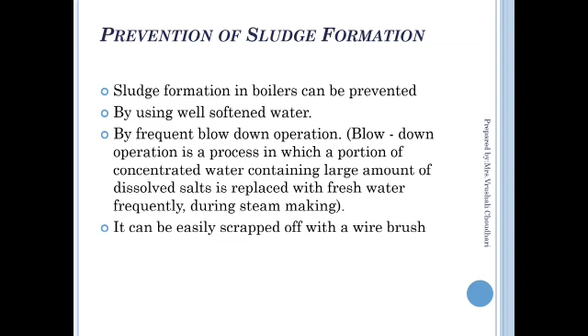Sludge is a soft, loose, slimy precipitate, while scale is a hard deposit. When sludge forms, it is non-adherent. It is not going to stick on the walls. It is going to float on the surface of the water. While the scale is firmly deposited on the inner surface of the boiler and difficult to remove.